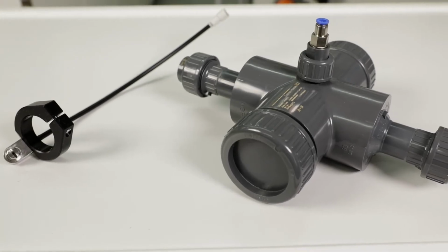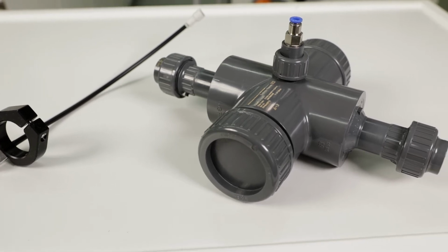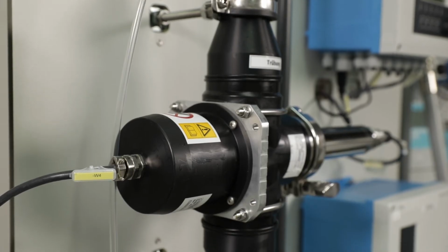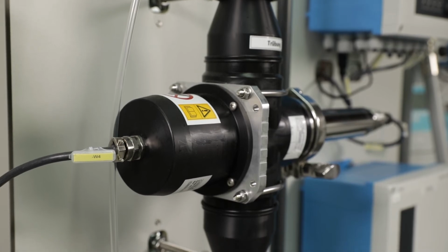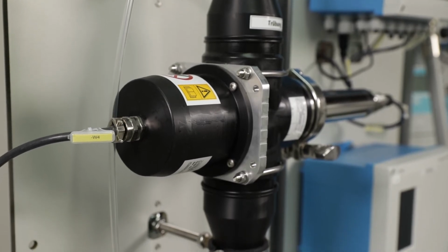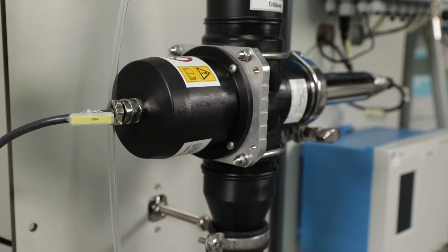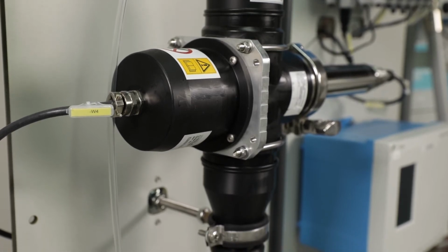To minimize your effort for manual cleaning and to prevent deposits or the accumulation of air bubbles, we recommend to use an automatically controlled cleaning unit. Basically, there are two different options: compressed air or ultrasonic. The cleaning power of compressed air is more effective. However, the advantage of ultrasonic cleaning is that the cleaning unit does not come into contact with the process medium and can therefore be used in hygienic applications. I will now explain these two cleaning methods.